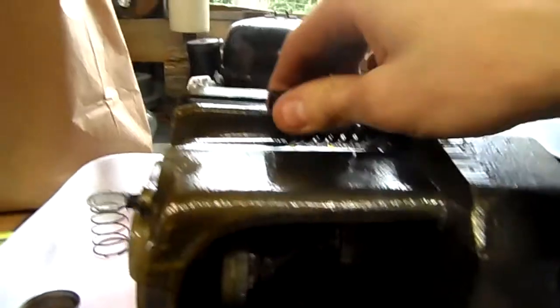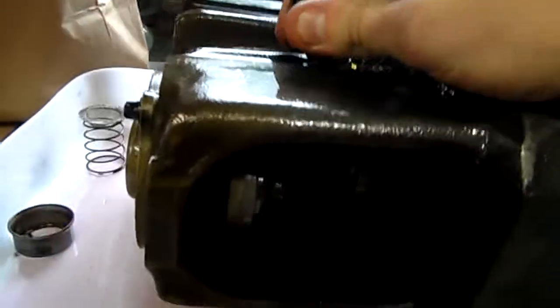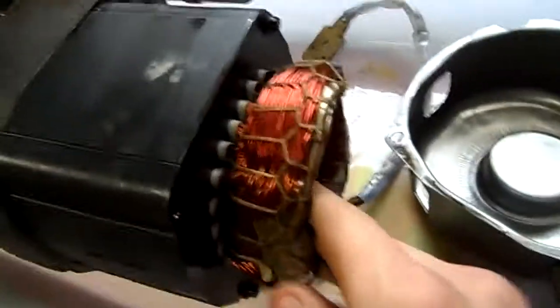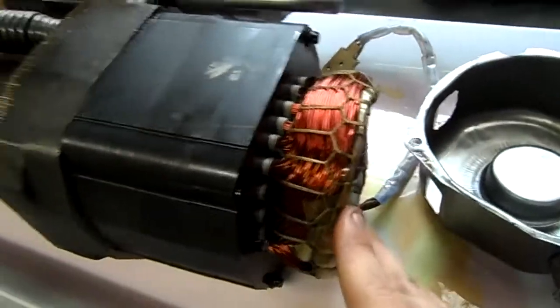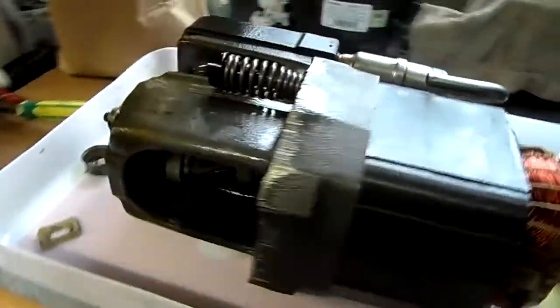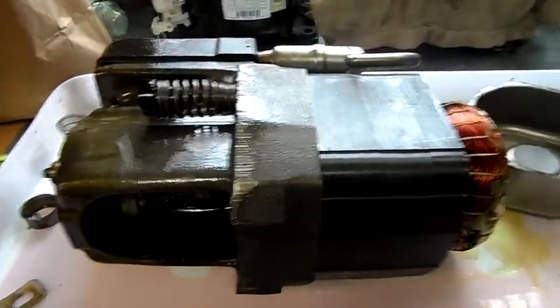And there's the head on the other side here. Neither of these springs are broken — the suspension springs — which is a good sign because it means a loud noise probably isn't why they condemned it. I'm guessing it's probably motor issues; the stator might have a minute short in it somewhere. I'll take the other side off and find out.